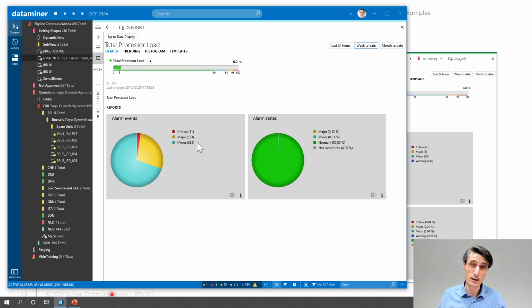I have generated hundreds of alarms in the last week, but it was only a fraction of the time in alarm. So I should revisit my alarm template here, because maybe I need to activate some hysteresis. There are probably some short toggling alarms whenever it spikes. And I can fix that with hysteresis, putting a delay on there.